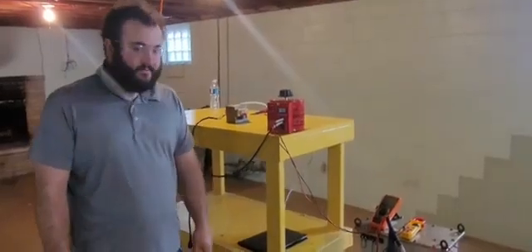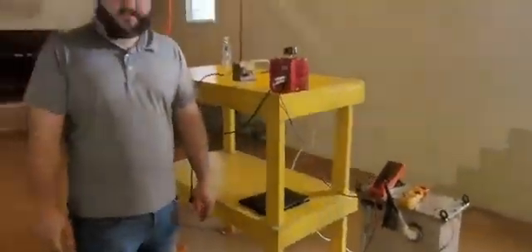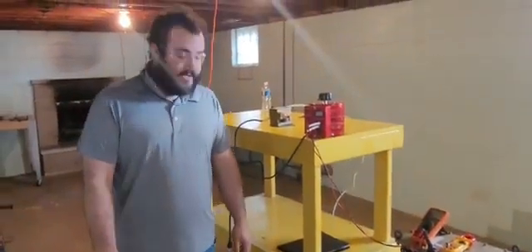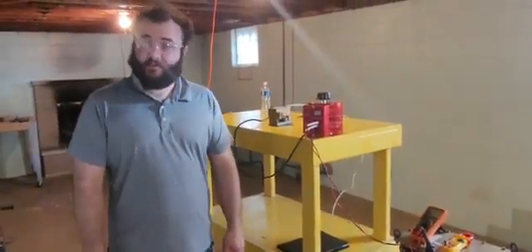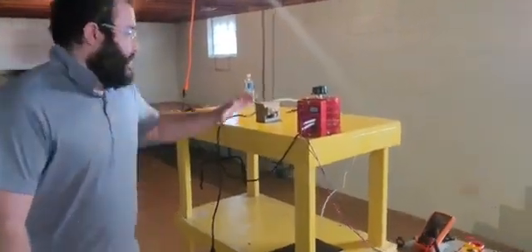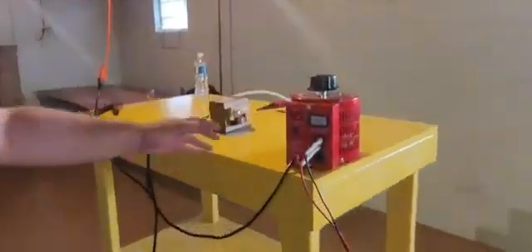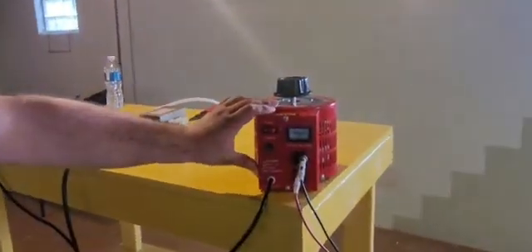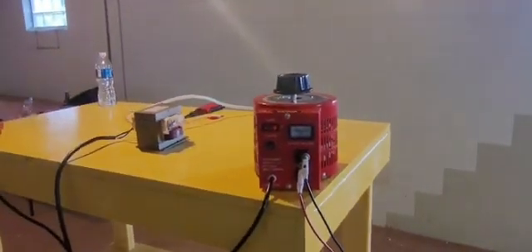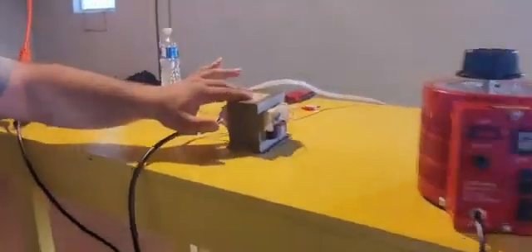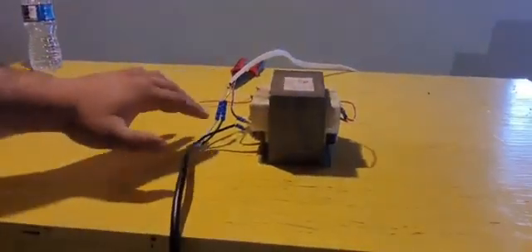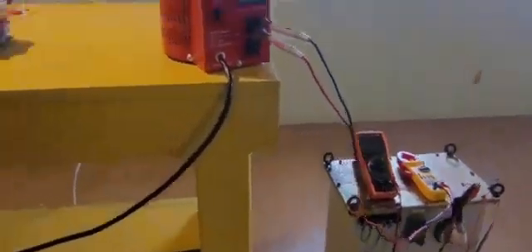I'll be showing everyone how an X-ray generator works. They call it an X-ray generator, even though it's really just a transformer with a very large diode on it. I have it hooked up to a variac, otherwise known as an auto transformer, to control the voltage input. And this here is a microwave oven transformer with the high voltage secondary shorted to the case, and the primary in series with the generator.